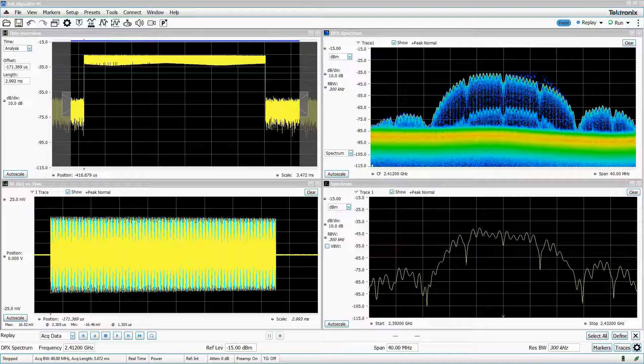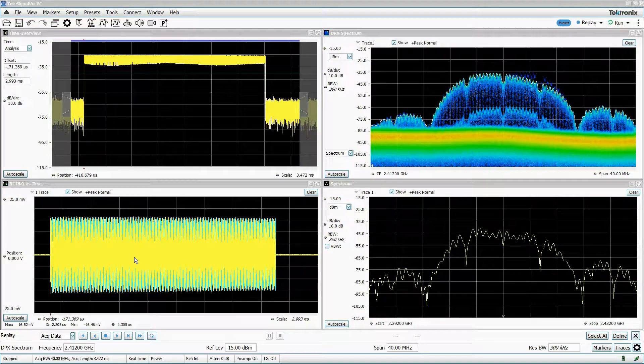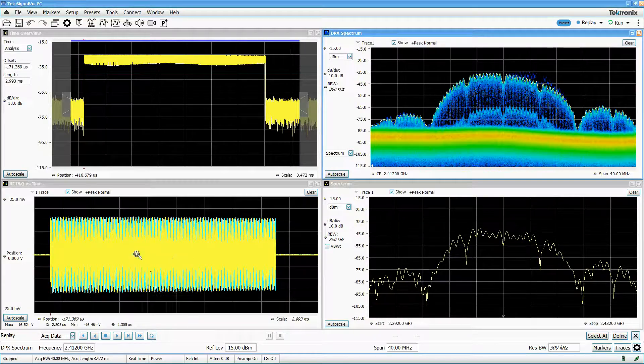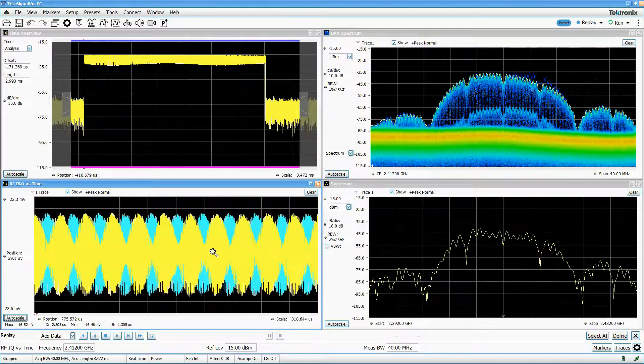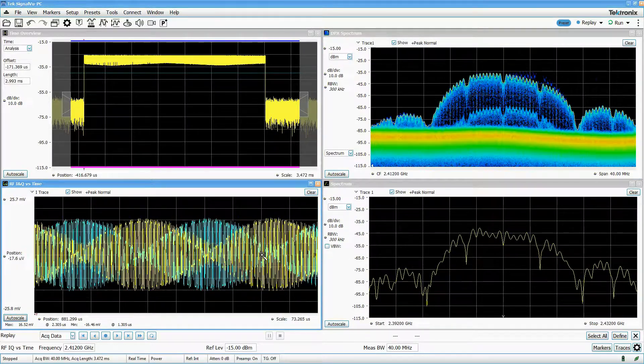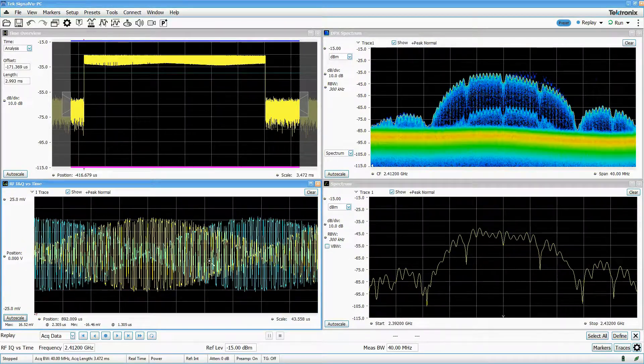There are two main methods to save data in SignalVu-PC: blocks of IQ data as .tiq files, and contiguous streaming IF data, which are .r3f files.